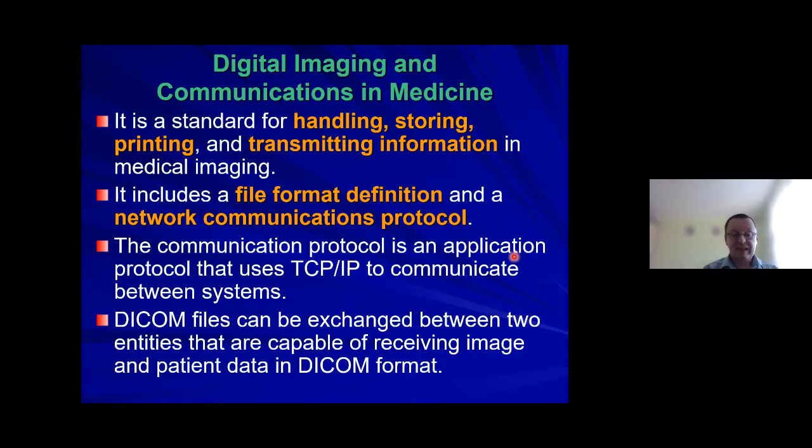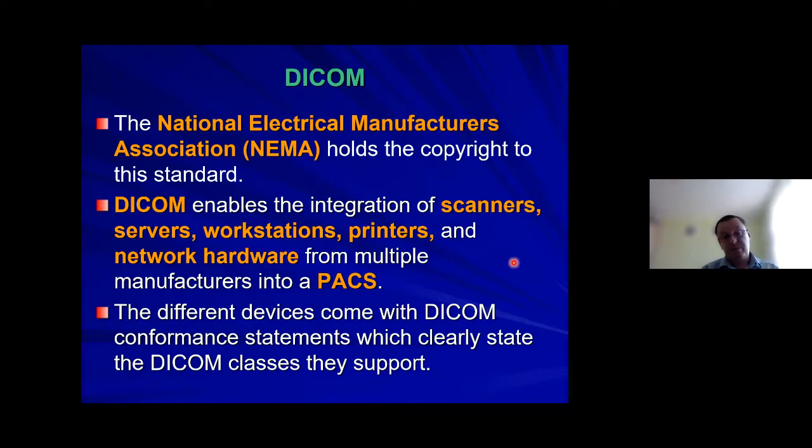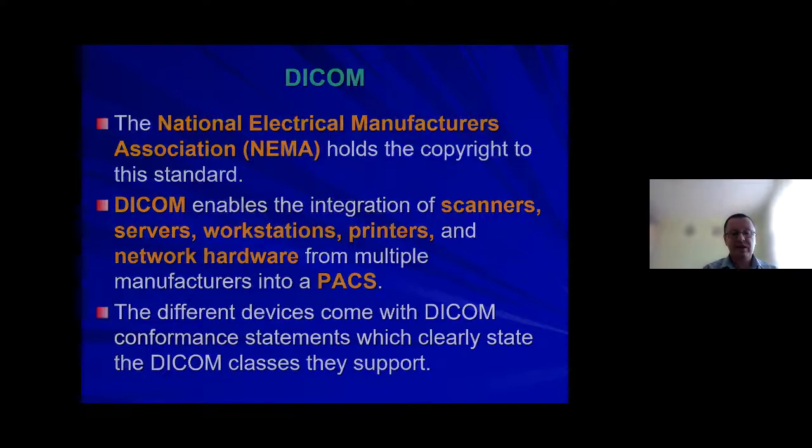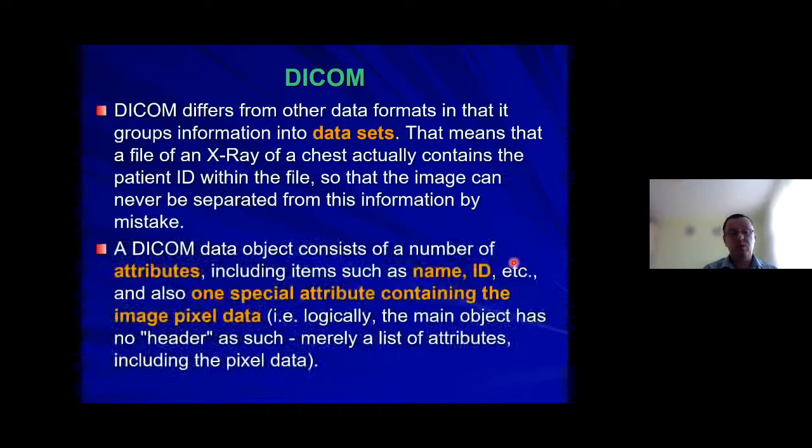It allows direct exchange of DICOM data sets between different systems, which are both capable of processing DICOM data. Copyright belongs to the National Electrical Manufacturers Association of the United States for this standard, and it allows integration of multiple devices into a single network and being connected to PACS.